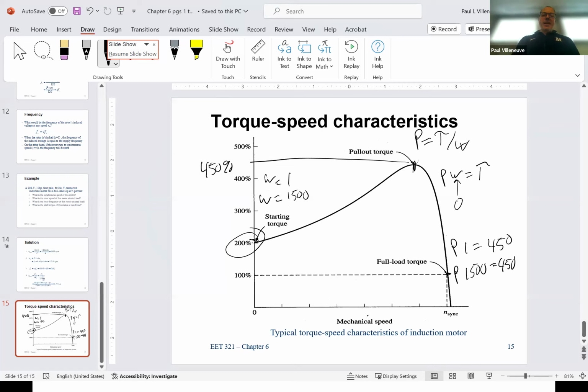So the whole reason I said that is to make sure everybody understands that way more current goes in at starting than even at the pull-out torque, and it has to do with the fact that you've got no speed. Once you get up to speed, it drops out. These machines actually get way more efficient when they run at higher speeds — the closer you get to synchronous speed, the more efficient the machine is. Good question.